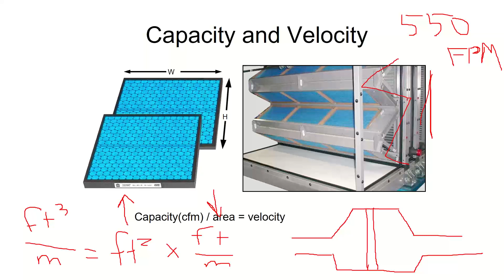I need to keep this at 500 feet per minute or less. Both the filter section and the cooling evaporator coil, I'm pretty much capped at 500, 550 feet per minute of velocity, or bad things happen. Bad things in the filter means I can't catch small stuff. Bad things on the evaporator coil means the water blows off the coil. I have enough velocity pressure to throw the water off the coil and slam it into the electrical section of the fan, which I don't want to happen. I need to slow it down, and V-banks are one way to get that done.